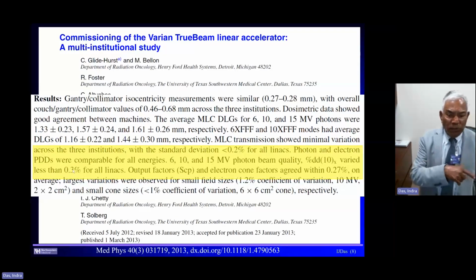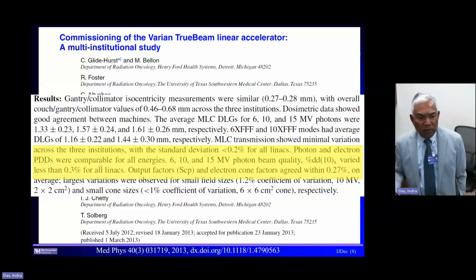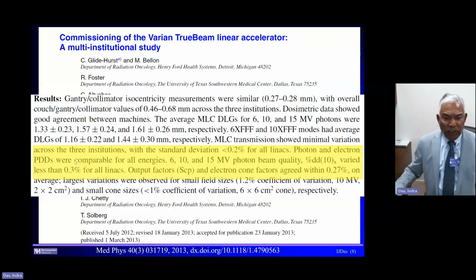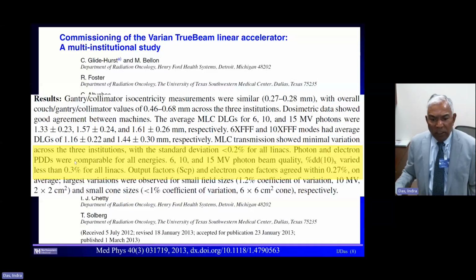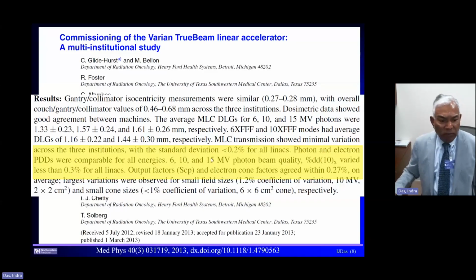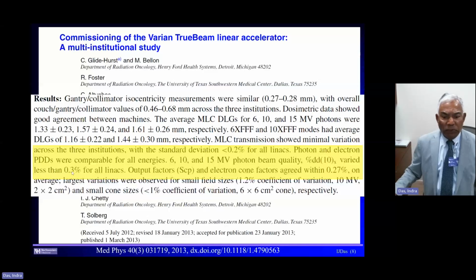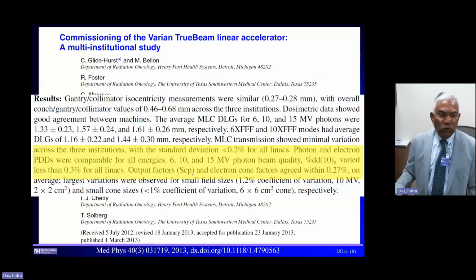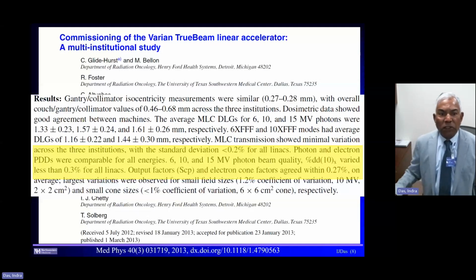Compared to the previous paper that I showed you, where significant deviations were there, here in this paper, for the 6, 10, and 15 MV beams, the differences in percent depth dose were only 0.3%. The rest of the other things are also within 3%. So it is very, very good to know that depth dose and these things are within 0.3% between multiple institutions of the same vintage, which is TrueBeam.